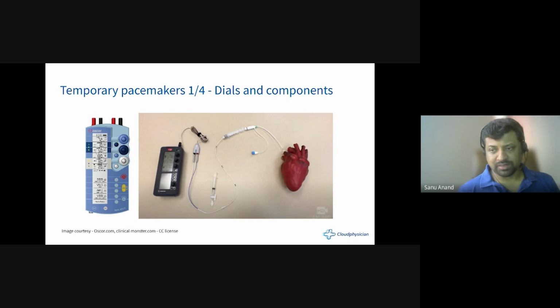You can see the pulse generator with the dials and all that, and then you have the 2 electrodes that you can see here, which is attached to the pulse generator. That's actually a part of the lead, and you can see all these black markings on the lead. Each of that will have a small black shade. There's 1, 2, 3, and each of that basically represents 10 centimeter each. One shade represents 10, and 2 represents 20, 3 30, and so on. And these markings are extremely important to keep an eye on when you're pushing the lead in.